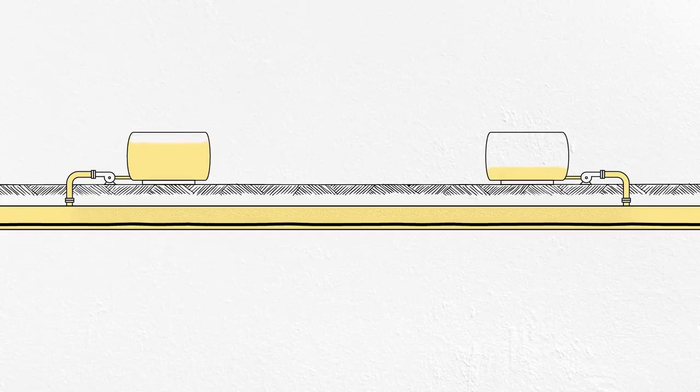The rating of a transmission line, in other words, how much power it can deliver, is almost entirely based on temperature. All conductors, with rare exceptions, have some resistance to the flow of electric current, and that creates heat, which will eventually damage the conductors and insulation if it builds up. The more heat you can remove, the more power you can push through the line. That's a major benefit of pipe-type oil-filled cables. They're surrounded by a gigantic liquid heat sink that can be circulated to keep the temperature down and prevent hot spots from forming in the lines.